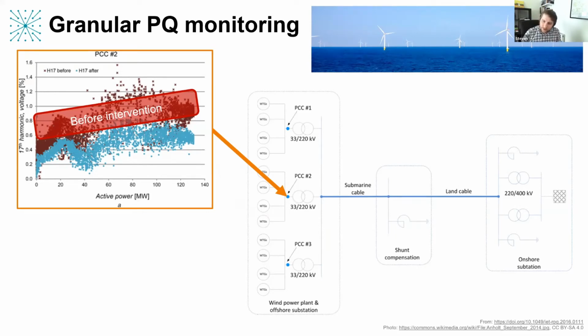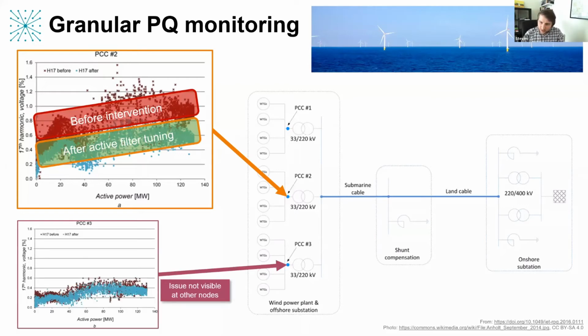With the visibility that this power quality monitoring regime provided, it was possible to detect that resonance and mitigate it through control of the filtering that was going on. You can see that after the intervention, after filter tuning, the 17th harmonic was brought down to acceptable levels. What's also interesting to note is that there was power quality monitoring at another location, which didn't see any impact from that harmonic. It wasn't an issue there because of the way the impedances worked out. There was no issue there.